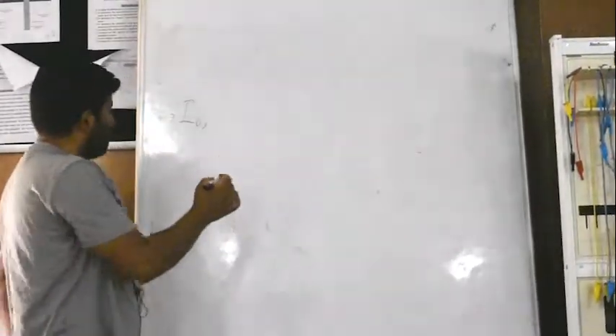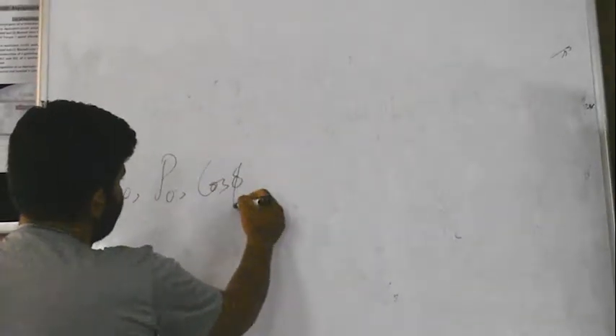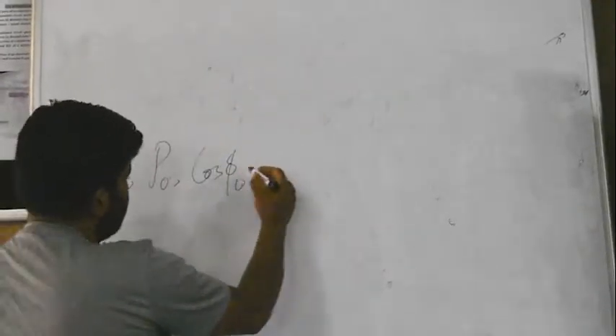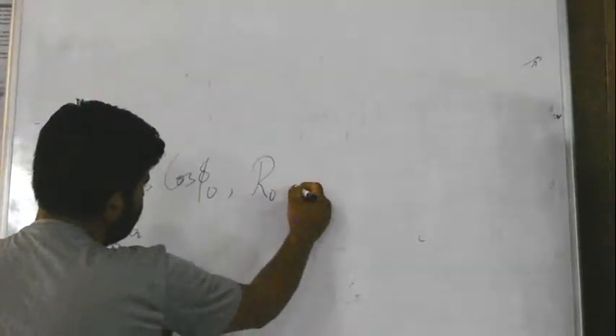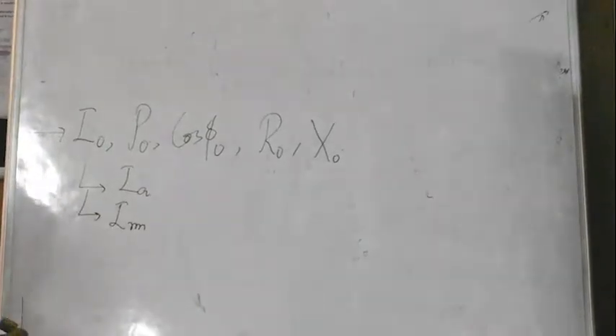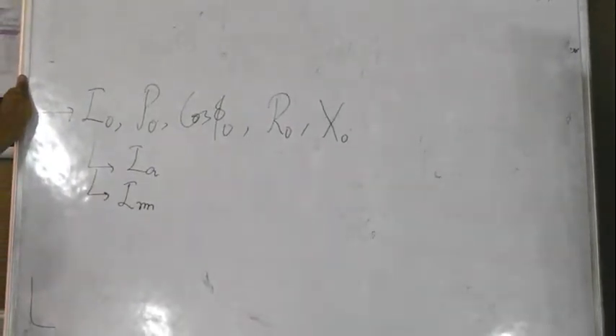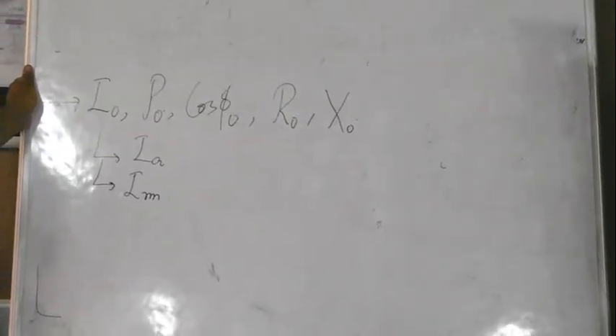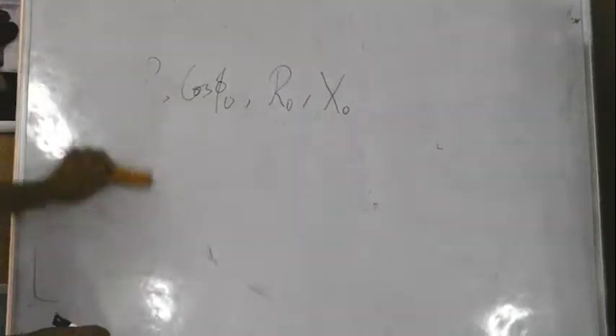First we see the no load current drawn by the single phase transformer. So these are all the parameters. First we see the no load current I naught, we see the core losses P naught, then we see the cos phi naught, the power factor at no load. After that we obtain the two components of this no load current, the active component Ia and the magnetizing component Im. Right, we have obtained this R naught and we have obtained this X naught. So these are all the parameters we have obtained by performing the no load test on a single phase transformer. After that, we will be showing you the same theoretical procedure for how we will be performing the short circuit test. Then after that we will be demonstrating it.